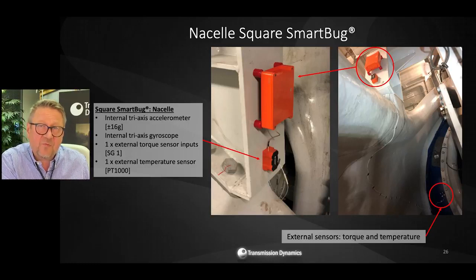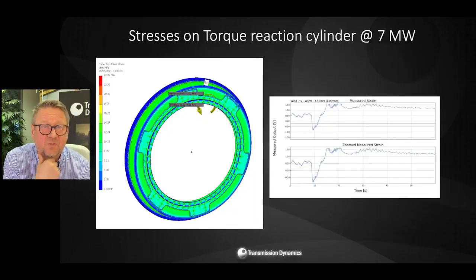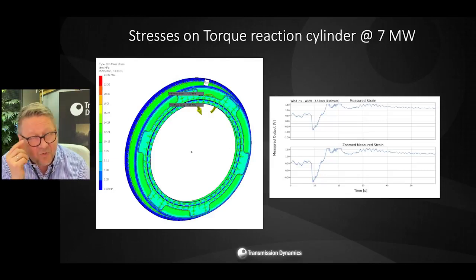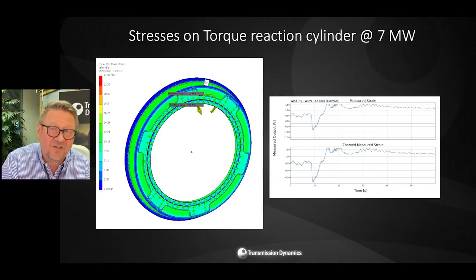Now, the Levenmouth wind turbine is more complicated than most wind turbines we normally deal with, because we don't have classical access to the input shaft. So what we needed to do is perform finite element modeling and calculate torque-induced stresses on the torque reaction flange, which is a circular disc, as opposed to classical torque reaction arms measuring torque directly on the rotating shaft.